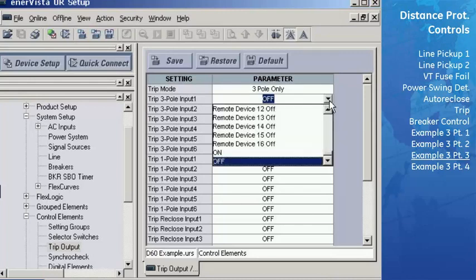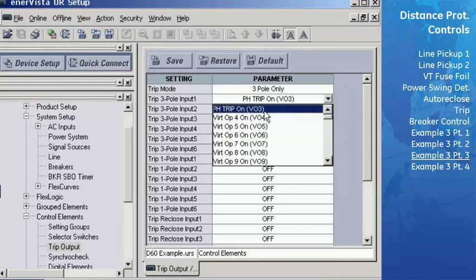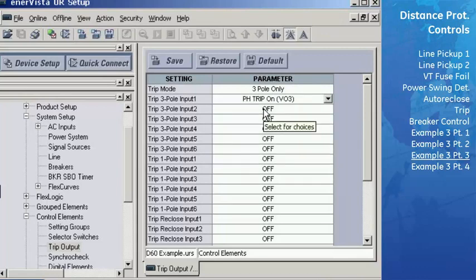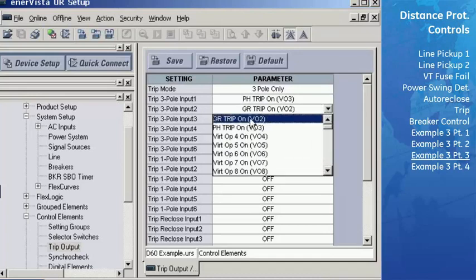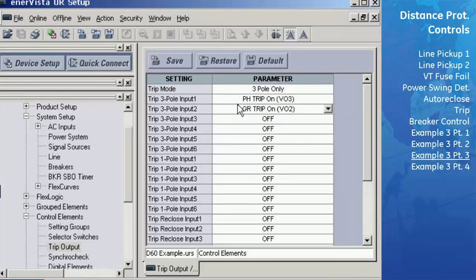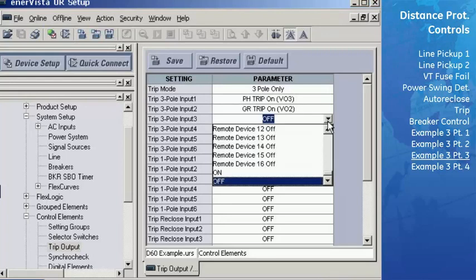In the Input 1 field, select Phase Trips, or Virtual Output 3, which was created in Example 2. This signal will turn on if any of the phase distance zones operate. Select Ground Trips, or Virtual Output 2 for Input 2. This signal was also created in Example 2 and will turn on if any ground distance zones operate. Select PUTT Operate for Input 3 to ensure a 3-pole trip occurs for a PUTT scheme operation.